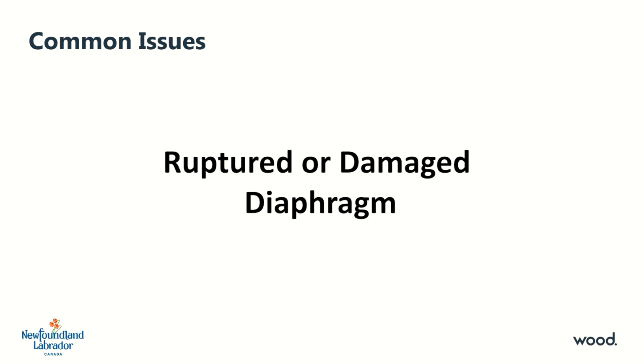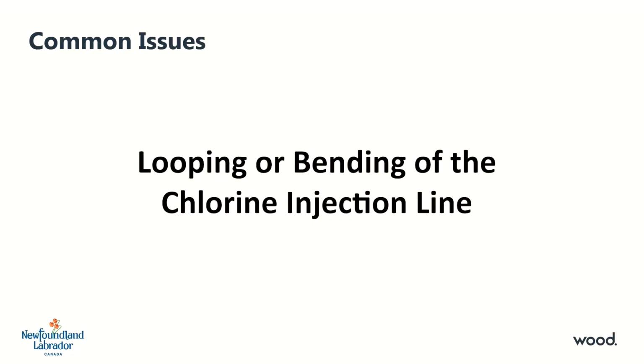The most common cause of a pump failure is a ruptured or damaged diaphragm. In some pumps, leakage can be seen from a weep hole in the bottom of the pump head when solution is forced through the leak in the diaphragm and then pressurized on the backstroke. Looping or bending of the chlorine injection line is a configuration issue where the chlorine injection line is either bent and restricting flow, or the force of gravity is working against the pump, reducing the rate of chlorine injection. Lines should be adjusted so that the flow is not restricted by pinching or mechanical obstruction.